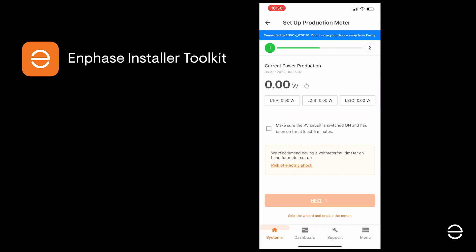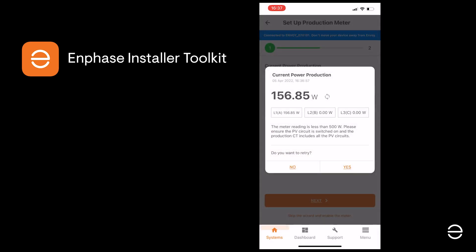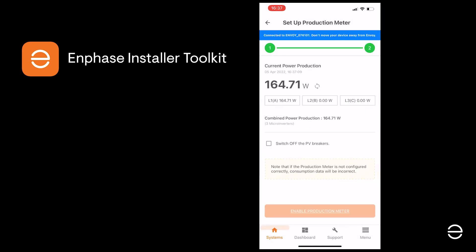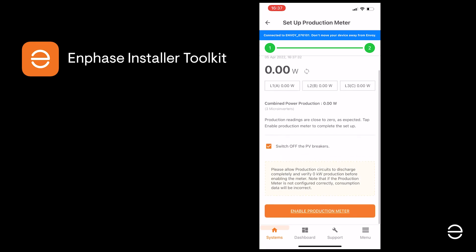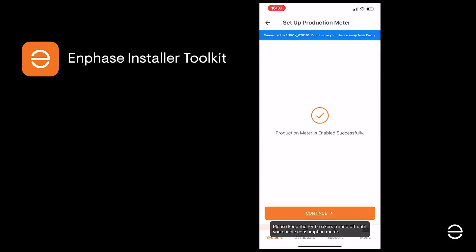We may need to wait a few minutes to see the production coming off the PV system. When that's the case, we can check the box to confirm the PV system is on and click Next. We need to wait until the production level corresponds to what we'd expect from the system at the current time of day, and when we're happy with that, we can move on. The next step is to switch off the PV circuit breakers to check that the production is zero and the system is correctly configured. If that's the case, we can check the box and enable the production meter.